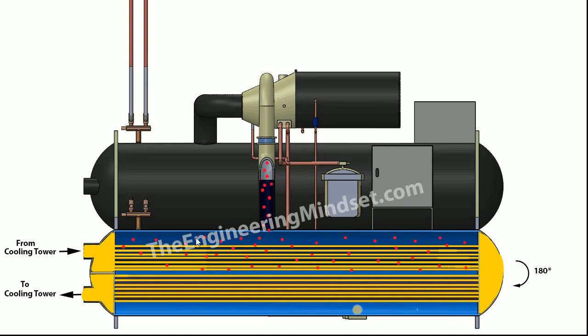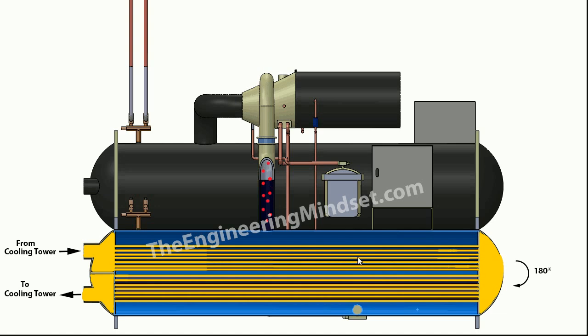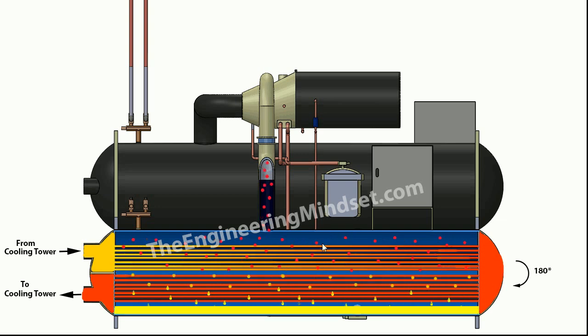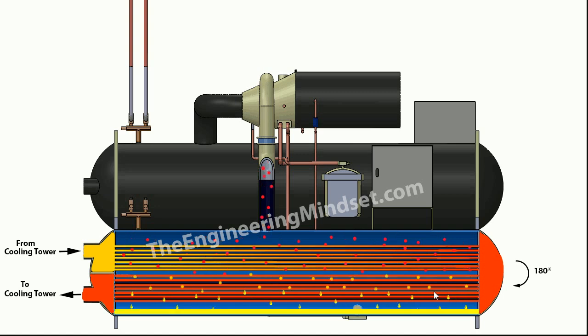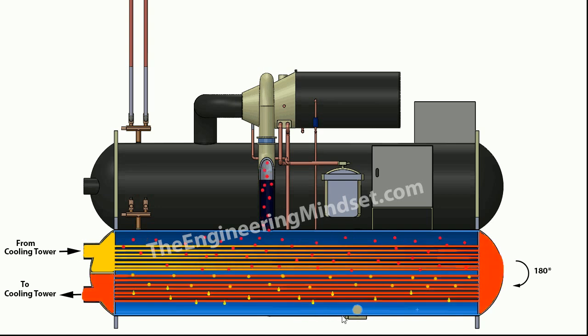The compressed refrigerant comes out of the compressor and starts to fill the void within the condenser. As the condenser water passes through the tubes, the particles of refrigerant start to hit against them, condense, and transfer their thermal energy through the pipe wall into the water. The condenser water changes colour to indicate it's picking up heat. It hits the water box, does a 180-degree turn, picking up the last heat it possibly can. The refrigerant then collects as a liquid in the bottom and leaves through the exit, heading towards the expansion valve.